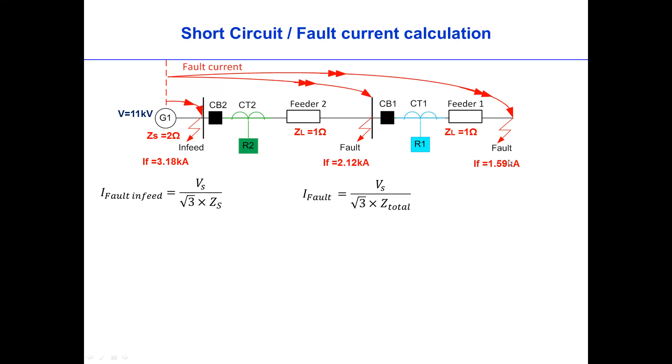And then finally, the fault current at remote end is calculated from the total impedance, which is source impedance plus line impedance of feeder two plus line impedance of feeder one. So now you can see the fault current is 1.59 kA.